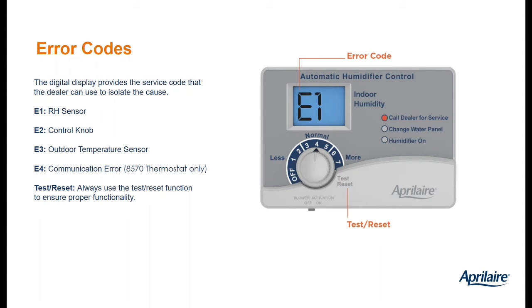E3, it's not getting a good resistance from the outside temperature sensor. Now I'll tell you right now, outside temperature sensors really don't go bad. So what this really is, almost always, is a loose wire. Either a loose wire at the humidistat or a loose wire at the wire nut that you used when you increased the run length on the outdoor temperature sensor. Rarely is the outside temperature sensor bad. So before you replace the outside temperature sensor or the humidistat, you're always going to turn that knob to test/reset and see if the error code goes away. In the case of an outside temperature sensor, I would just ohm it out. See if you're getting a short or an open circuit. That'll tell you if maybe you've got a nick in the wire and the bare leads are touching, or you've got a loose wire. Easy to fix, pretty straightforward.